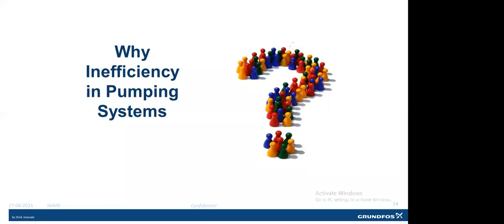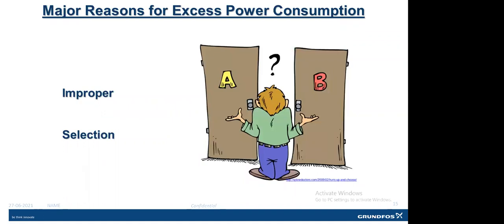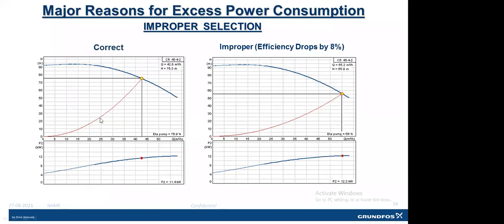Now next, we say yes, our pumps are not working efficiently. So what are the major reasons for inefficiency in the pumps? We will go one by one. First is improper selection. We need to always select the pump at the best efficiency point. For example, here we can see this pump is selected at 77% efficiency, and this pump is selected at 69% efficiency. Here we can say we have selected the pump at 8% lower efficiency.